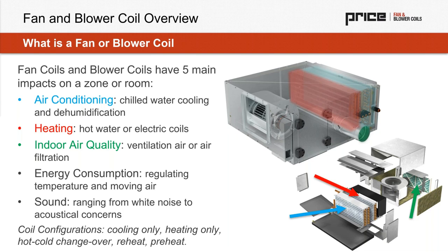So the other byproducts of fan and blower coils, which we need to be considerate of, are power consumption. That's an especially important one with code requirements that we see in market. So all of these have a fan and a motor. Making sure that motor runs efficiently and is happy is really paramount to making sure the whole building operates effectively.